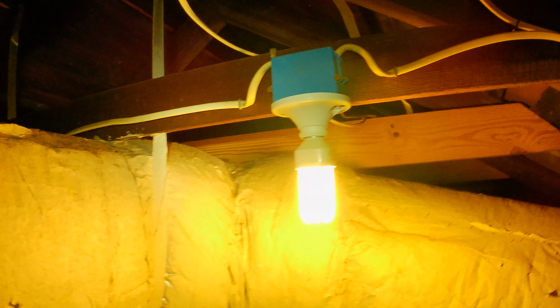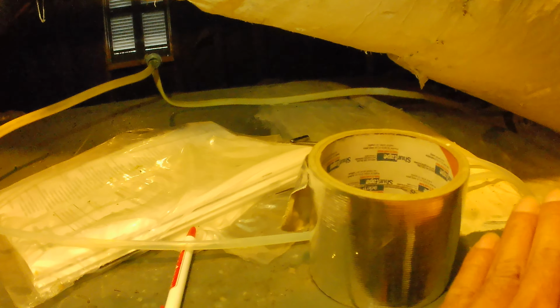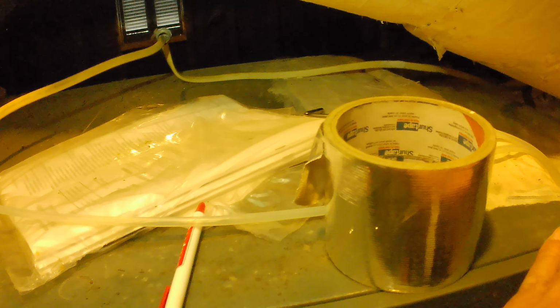Then we're gonna check for temperature difference, and this one is telling us that we should be between 40 and 70 degrees of temperature rise. So meaning that after reading the temperatures on the return and the supply, we need to be within that range. Anything greater than 70 is telling us something is going on, and airflow is being restricted on the coil side. And if it's below 40, then we need more air.